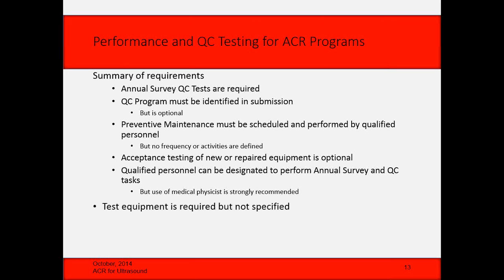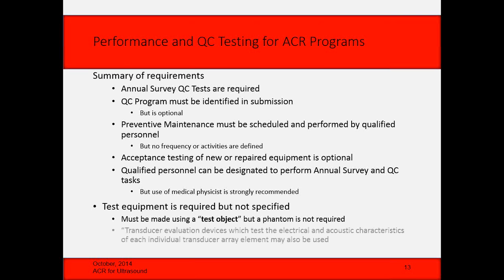Test equipment is required, but it is not specified. So what it says now is you must use a test object, but it actually says a phantom is not required. It also goes on to say there are transducer evaluation devices which test the characteristics of each transducer element, and those may also be used, but it can't replace any of the required tests because the system isn't a part of the test in those cases, right?